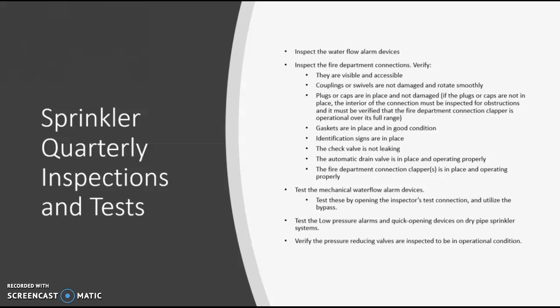The interior of the connection must be looked at. Make sure that the fire department connection clapper is operational over its full range, the full extent. We need to make sure that all gaskets are in place and they have a good condition on them. That way there is no leakage later on. Naturally, identification signs need to be in place. You need to know what is where and that it's all labeled. Any leaks whatsoever, let alone the check valve, the automatic drain valve is in place and operating properly. The fire department connection clapper is in place and operating properly.